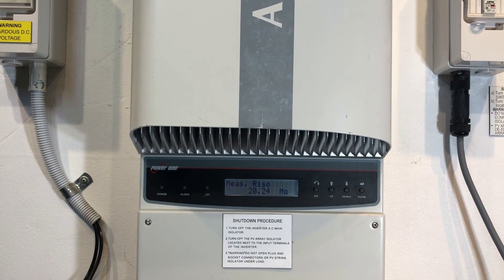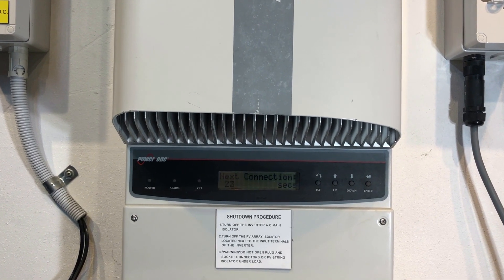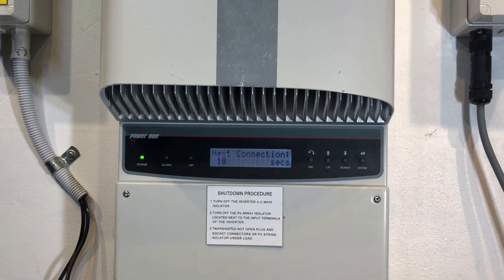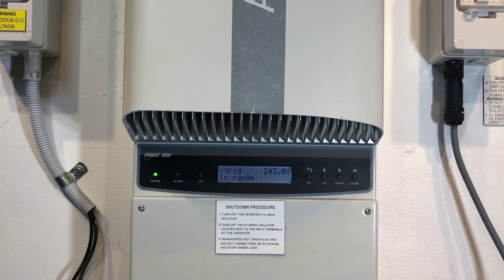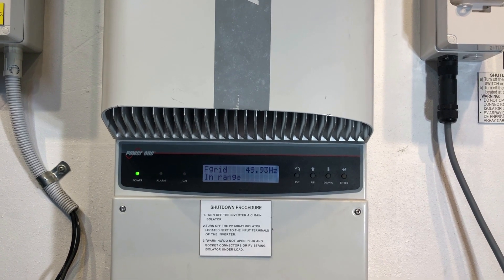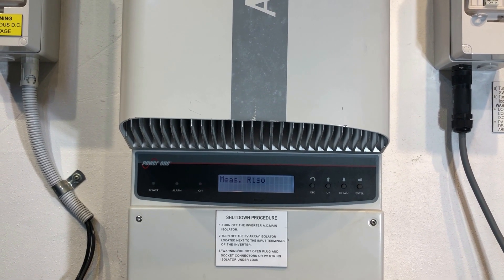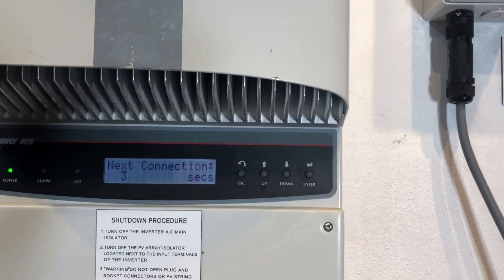So if your inverter is coming up with an E020 error like this one, it is an internal error and it will need to be replaced. It is an issue which is covered under the warranty of the inverter. Most Aurora inverters came with a five-year warranty, so if it was installed within the last five years, you will be able to make a warranty claim and get it replaced at no cost to yourself.